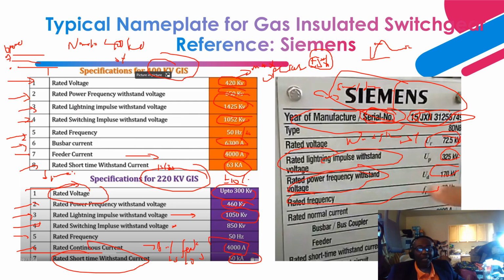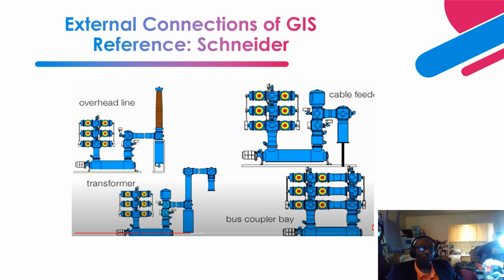Then your rated normal current for the bus bar or the bus coupler. The bus coupler is usually a tie breaker that ties, let's say you have 2 bus bars, and in between them you want a tie. That is when you utilize the bus coupler to tie the 2 buses. Next is the line side, the feeder. That is the rated current for the line side. Then the short circuit current.